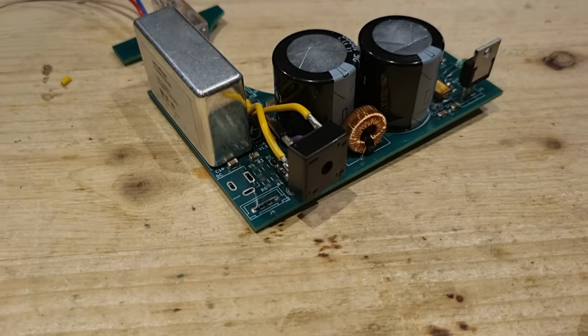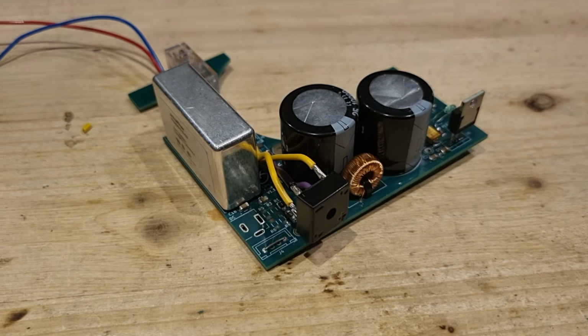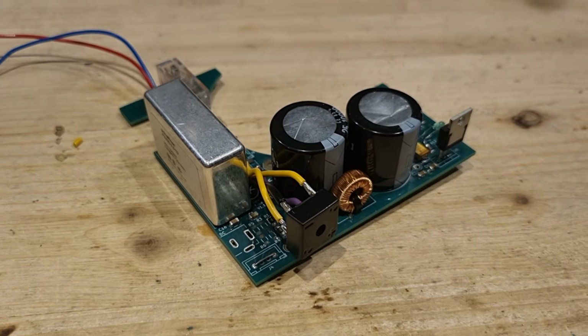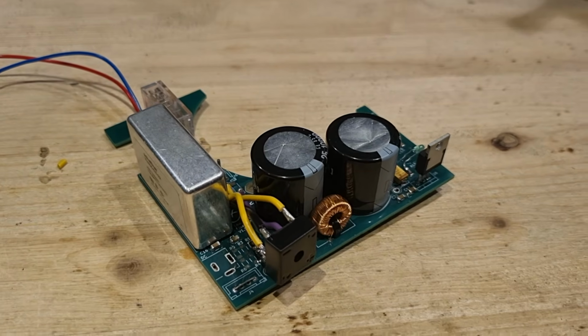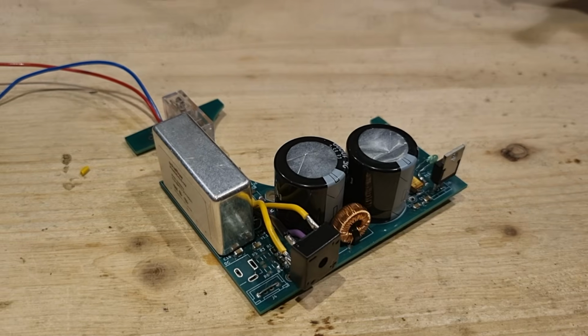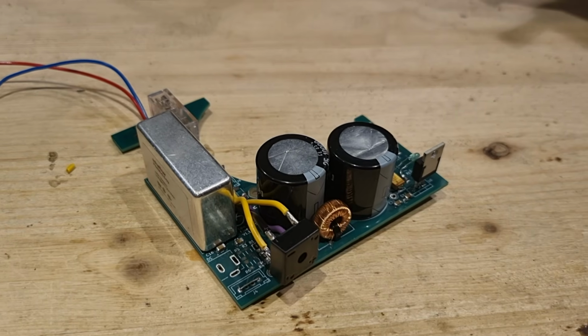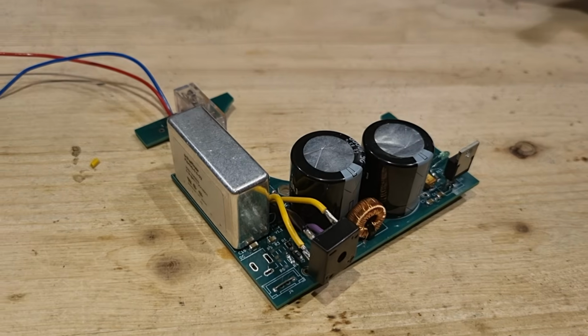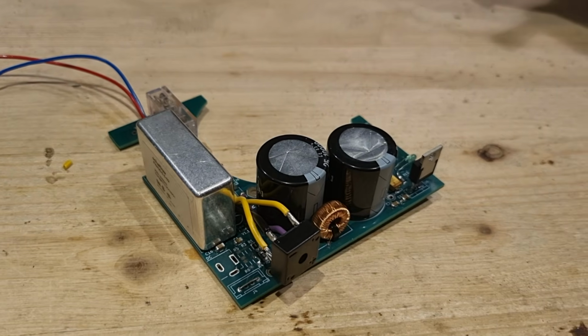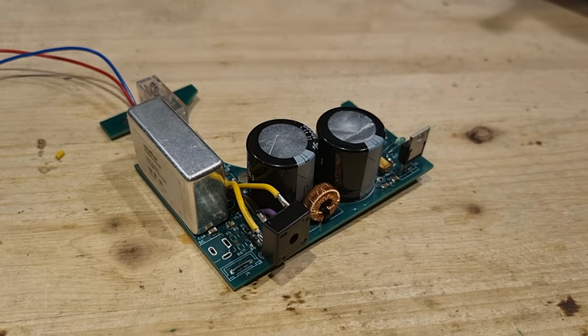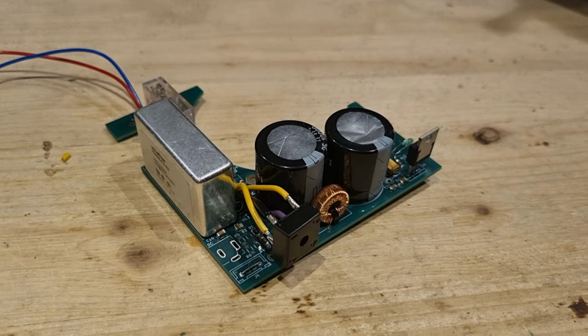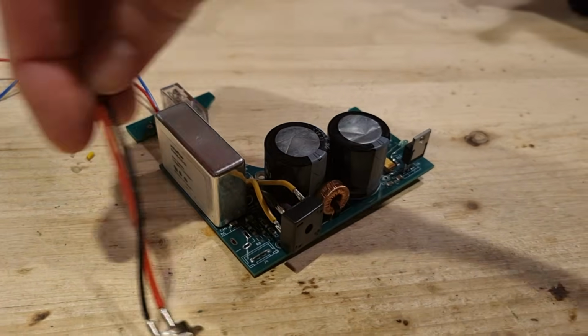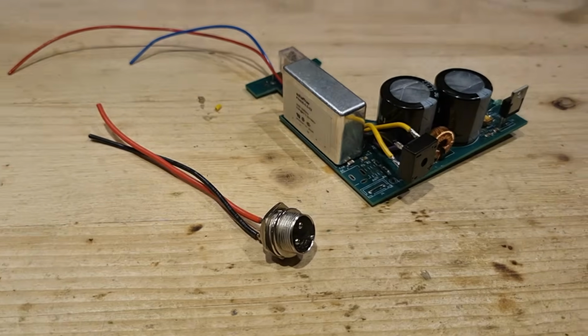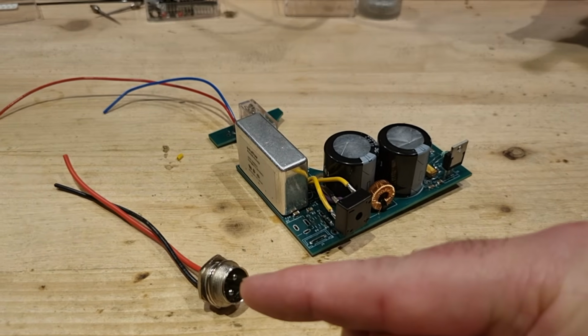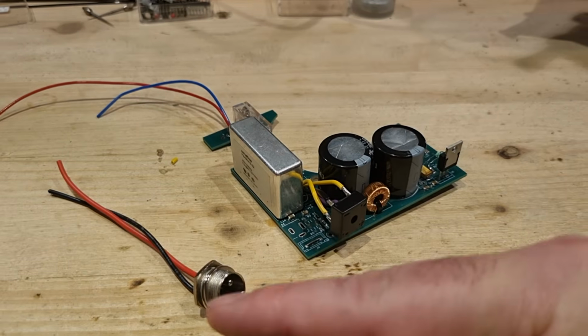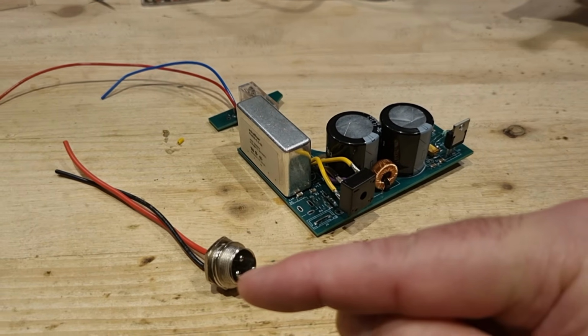The first is I need to get that output to my equipment. The typical way of doing that would be a standard 5.5mm to 2.1mm DC jack cable. That's great, but if that cable routes past other equipment, such as noisy mains cables or electrical equipment with interference, it can pick up noise as well. So you want a screened cable, which is why I switched to these connectors. This is a standard aerospace connector with 2 pins, one for positive voltage, one for 0 volts, and importantly, a case.